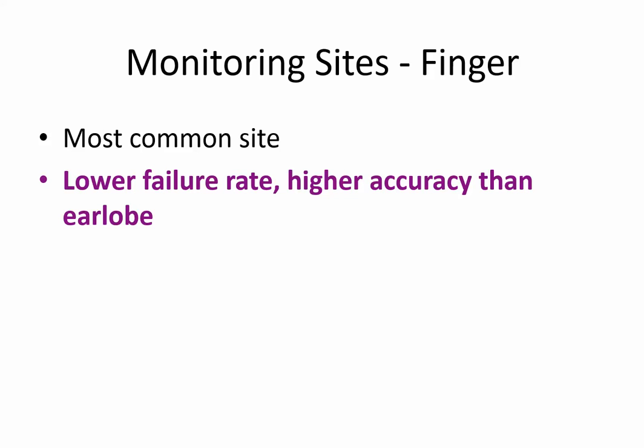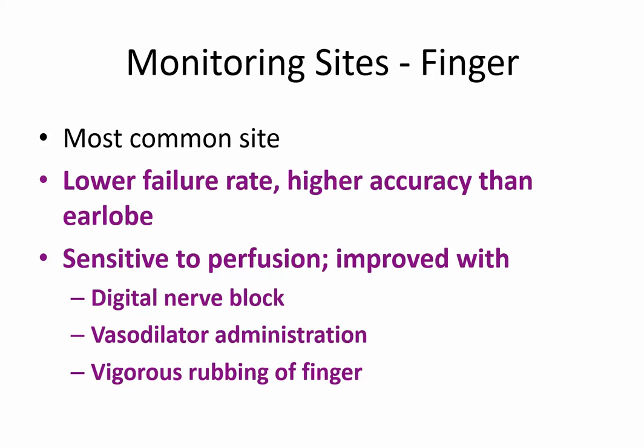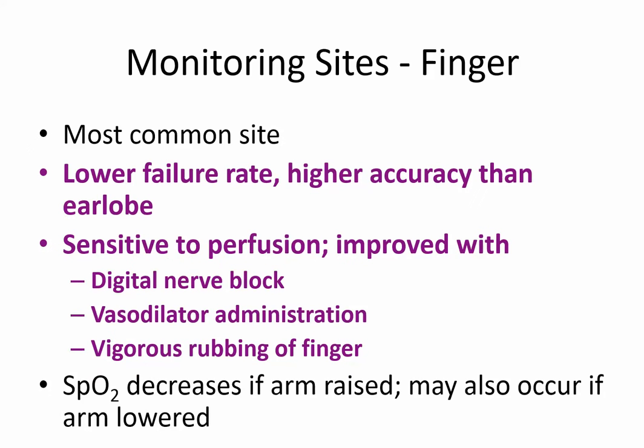Obviously, the finger's most common site. It has a low failure rate and higher accuracy than the earlobe, but is sensitive to perfusion. You can improve the detection by doing things that improve perfusion, such as a digital nerve block or administration of a vasodilator, or simply rubbing the finger. The pulse oximetry value decreases if the arm is raised or lowered.